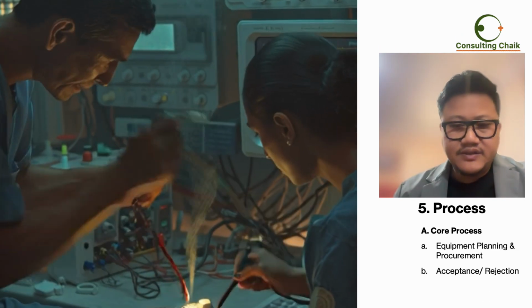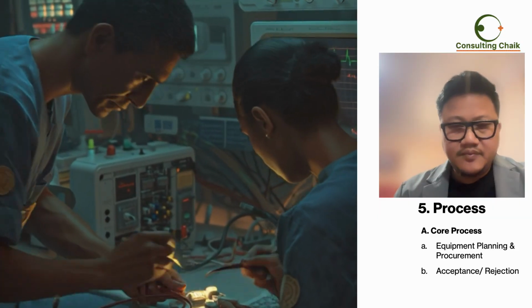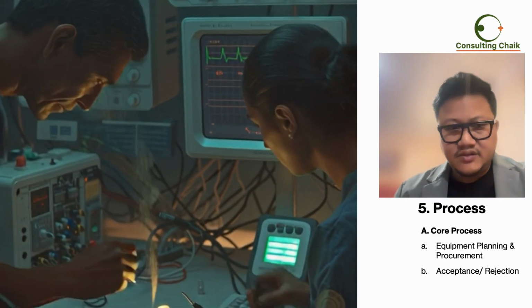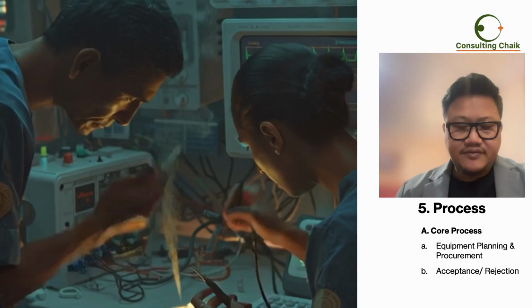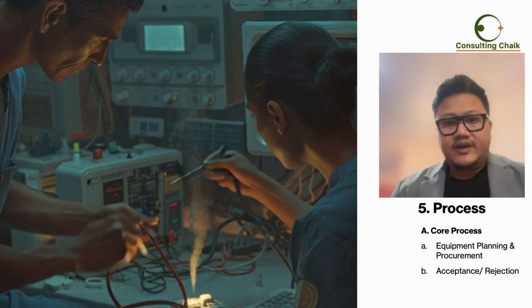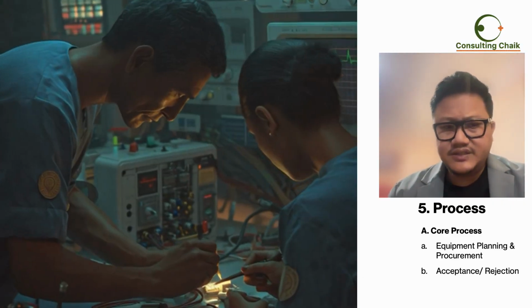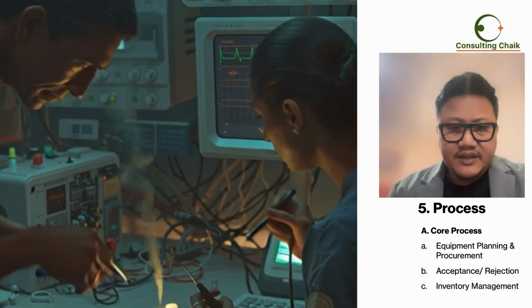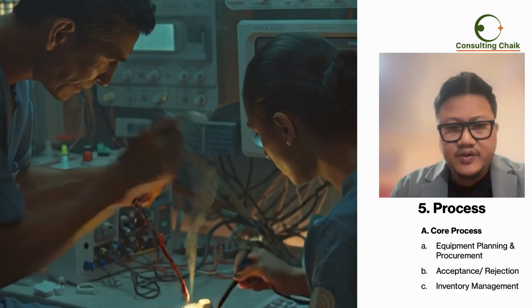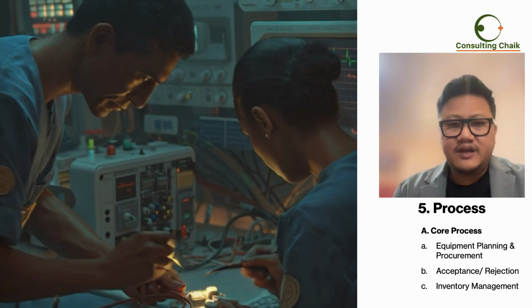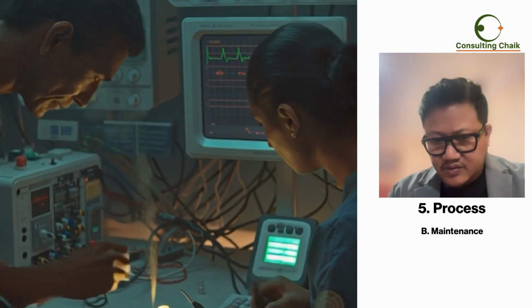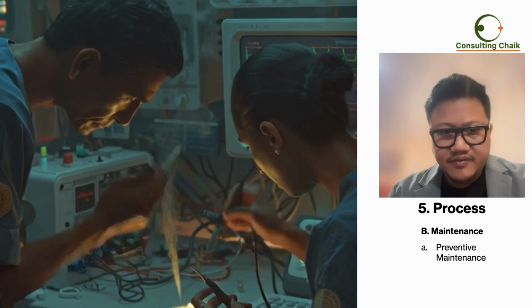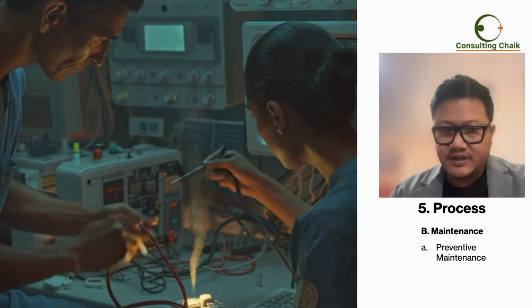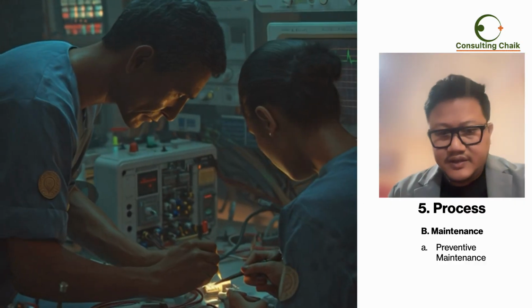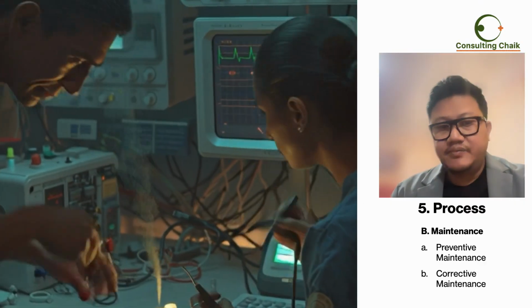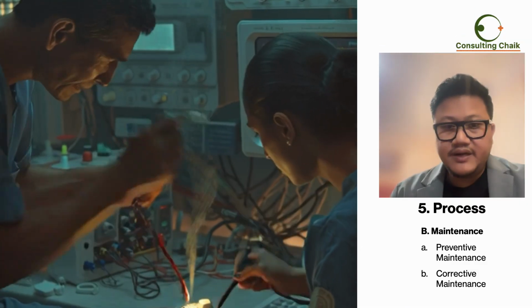And then inspection and rejection. When you have ordered the equipment, it comes to your hospital, you need to inspect. So unboxing checks, your performance verification as per, and whether they have provided it as per specs. Okay. Safety testing, user training coordination, all this is required. Then inventory management, your asset tagging, so barcode or QR code you are doing, location tracking, your annual inventory audits, all this. Now in terms of maintenance, you have PM, preventive maintenance, which is scheduled calibration service as per manufacturer intervals. Then you have your corrective maintenance, which is like breakdown repairs, troubleshooting, part replacement or post-repair testing.